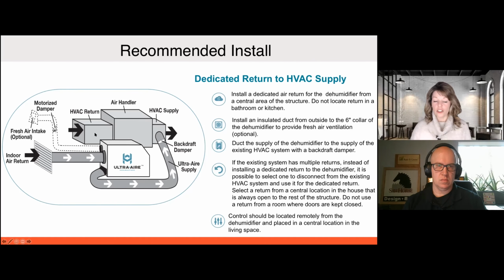You can no longer do in Florida a return to return install. That has always been our least recommended. Sometimes it's the only one you can do, but they are not allowing that anymore. And the reason being is Florida Solar Energy came out with a study in 2018 on dehumidifier installs, and they concluded that the return to return install is the most ineffective and inefficient way to install a dehumidifier. Reason being, dehumidifiers generate heat as a byproduct of removing water. If you blow that heat over the coils in the air conditioner, you are reducing the amount of water that the air conditioner can remove.